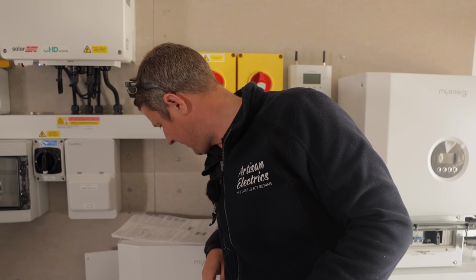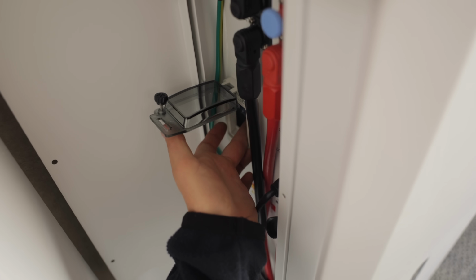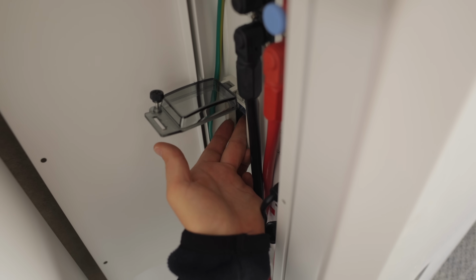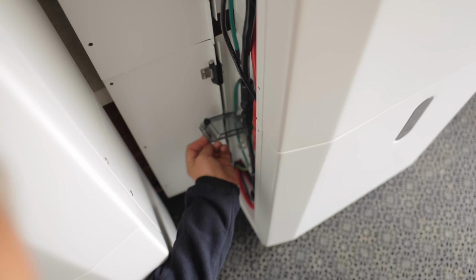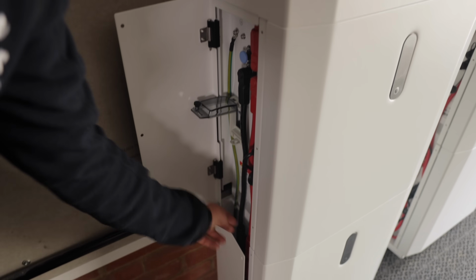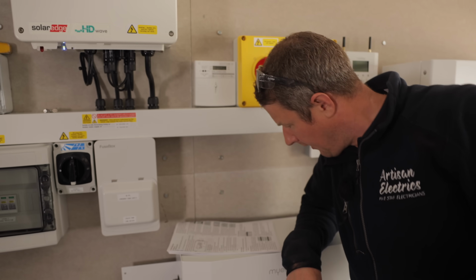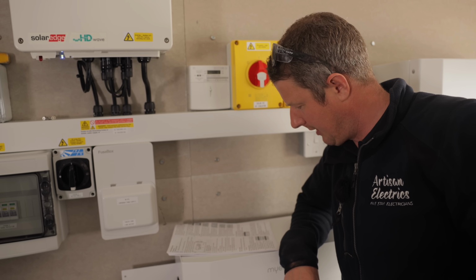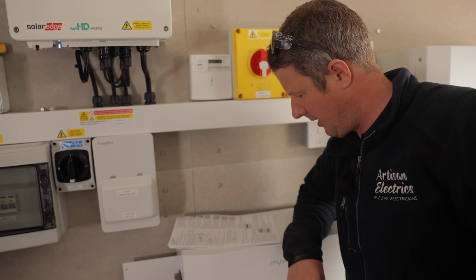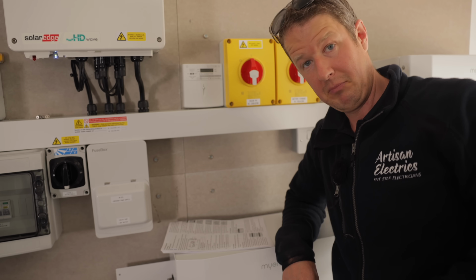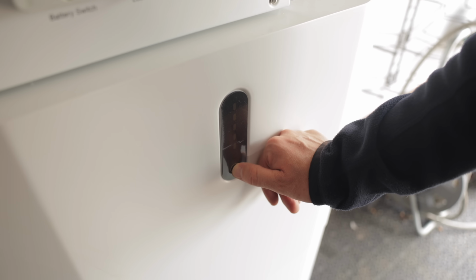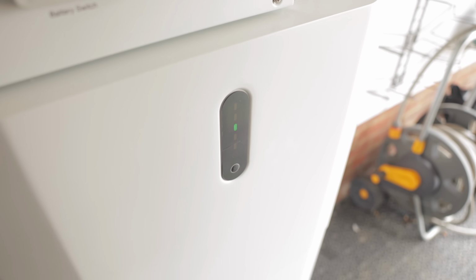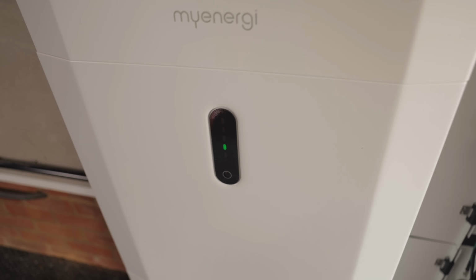Then we're going to turn on all of the battery DC switches on the side of the battery modules. So these are here. You can see they're labeled DC switch, and there's a surge protector, a circuit breaker in there. We just turn that on one by one, turn all of them on. So those are all on now. Then we're going to press and hold the power button on any battery until the indicator light turns on. If you have more than one battery in the system, you only need to press the power button on one of them. Okay, so we'll do that on the main battery. There we go. The others will turn on. And then the others will talk to each other and turn on.